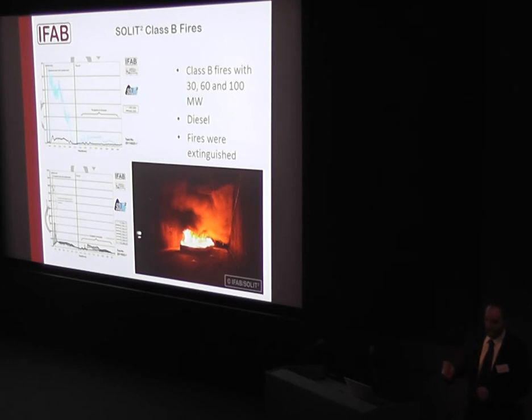When the fire is out, then you go in, again a little bit of gasoline, and then you start to reignite the pool, and then you see if the fire was just extinguished because it was running out of fuel or because it was extinguished by the system. But that's not the normal case, because most of the tunnel fires are hidden fires, and no system ever, no foam system, no deluge system, and also no water mist system really can extinguish these fires. Come to that, why this is so important, we'll come to that later.